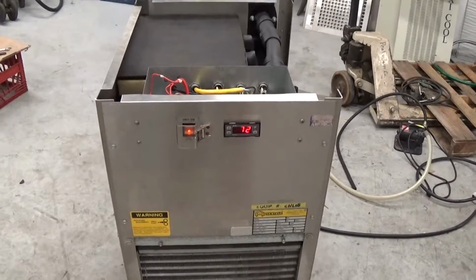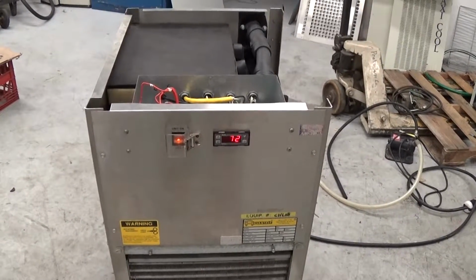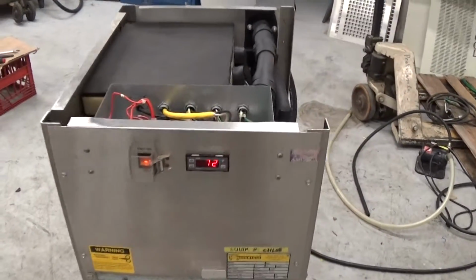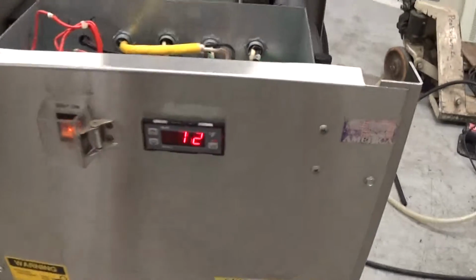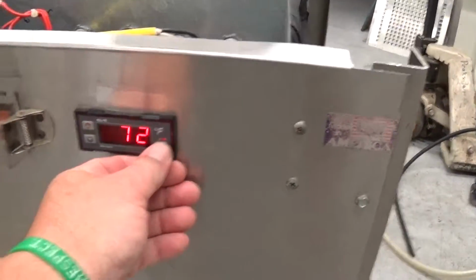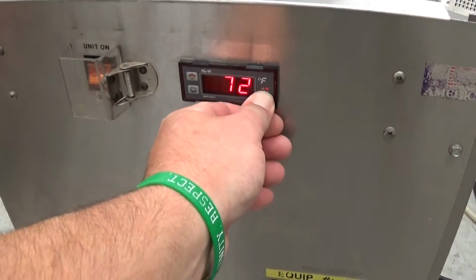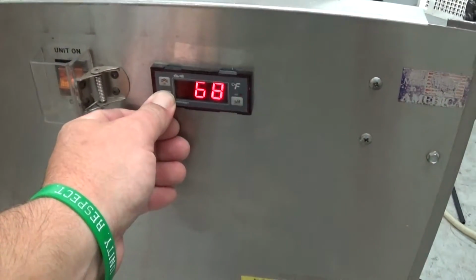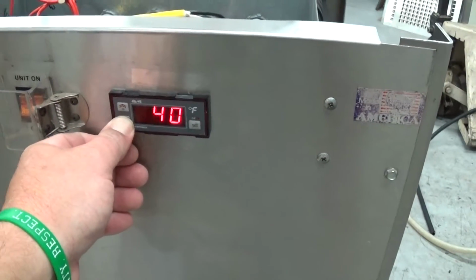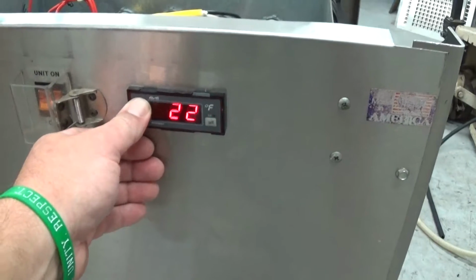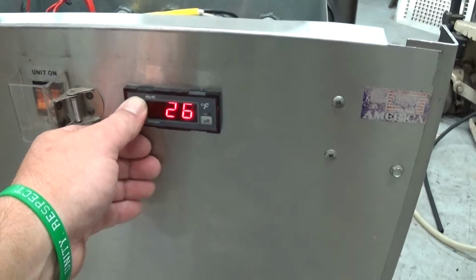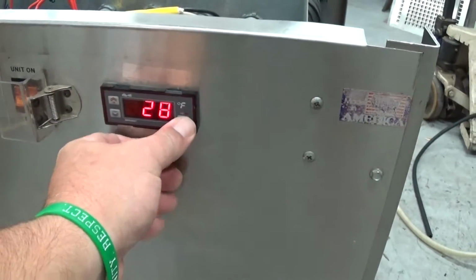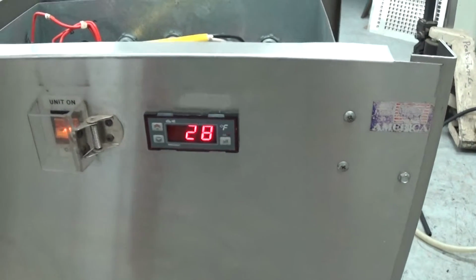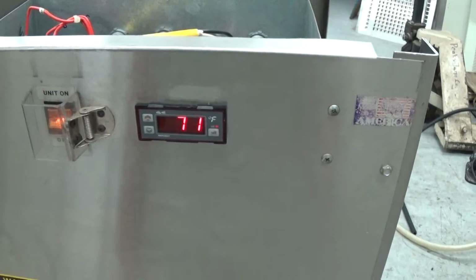And right now it's about 7 o'clock in the morning here. We just let it warm up overnight so we can see it chill down. Very simple. Take your set point, bring it down. You can actually go down to 20. Do not do that. That's a little bit too cold. 28's usually your desired set point for a brewery.